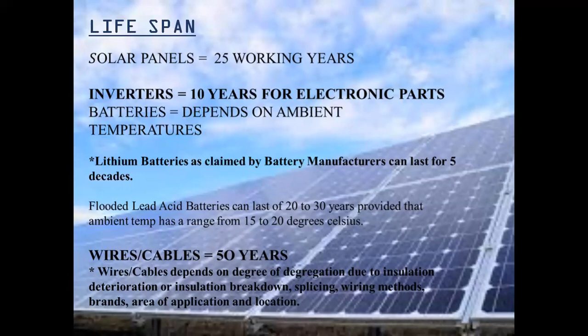We also discussed the lifespan. Solar panels have 25 working years; after that, the efficiency of your system decreases. For inverters, some manufacturers claim 10 years for services, parts and services. Lithium batteries, manufacturers claim 5 decades, so 50 years. Flooded batteries are 20 to 30 years, provided the ambient temperature is 15 to 20 degrees, as I said earlier. Our wires are rated for 50 years.